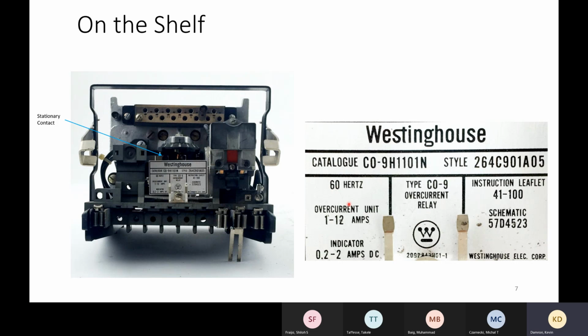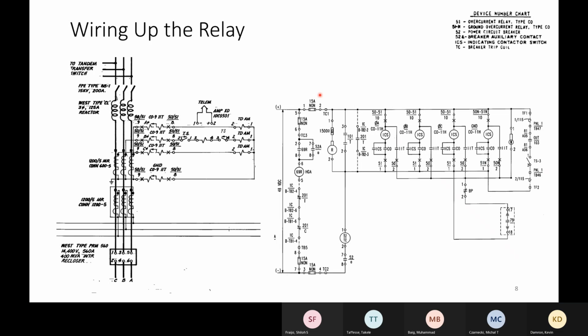So it shows you it's a 60 hertz relay. It's a 1 to 12 amp secondary. There's an indicating circuit that's 0.2 to 2 amps. And it's a CO9. Here's the instruction manual, and here's the schematic for it. The one thing to note here, and I'll talk more about it in a little bit, is there is a stationary contact right here. This is the best picture I had, so I thought I'd go ahead and identify where that was at.